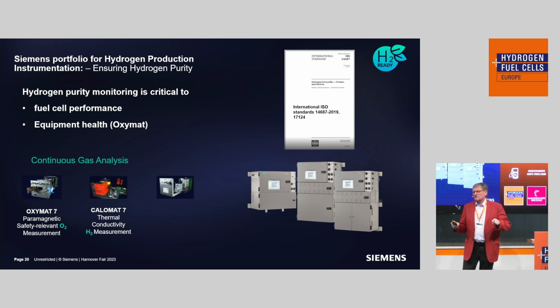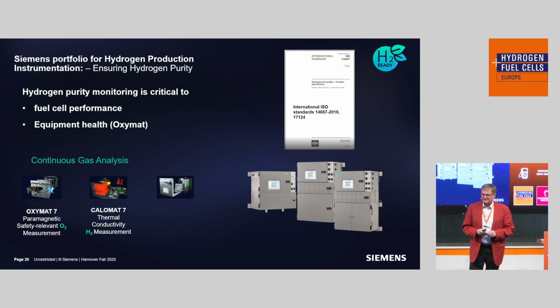But more important for the electrolyzer is equipment health. When there is a bad membrane, for example, you would see oxygen on the hydrogen side. We measure this with Oxymat. And since this is an explosive mixture, this measurement is ATEX certified and SIL rated.